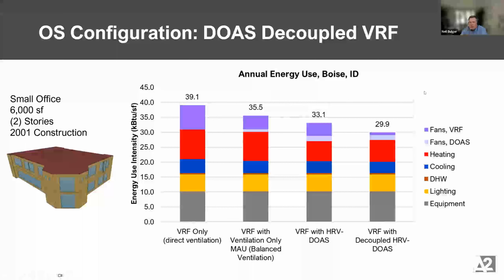So when we do that, we can see our VRF fan energy almost goes to nothing. Less than one. Kind of what we saw in those field demonstrations I showed. Strangely enough, not strangely enough, but it always looks strange at first, and then I think about it more. So that fan energy was turning into fan heat. And so now we need to make up some of that heat. We need to run the compressors a bit more. There's not any free heat from the fans entering our rooms. But sort of the pathway to low energy.